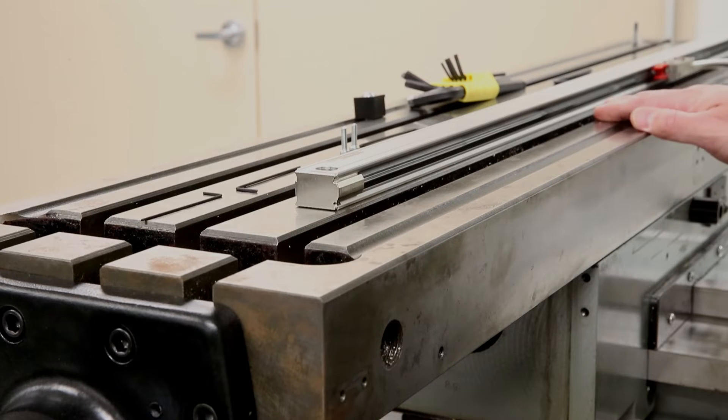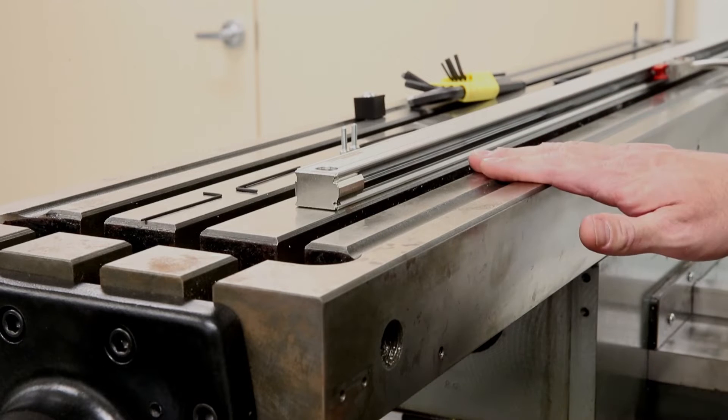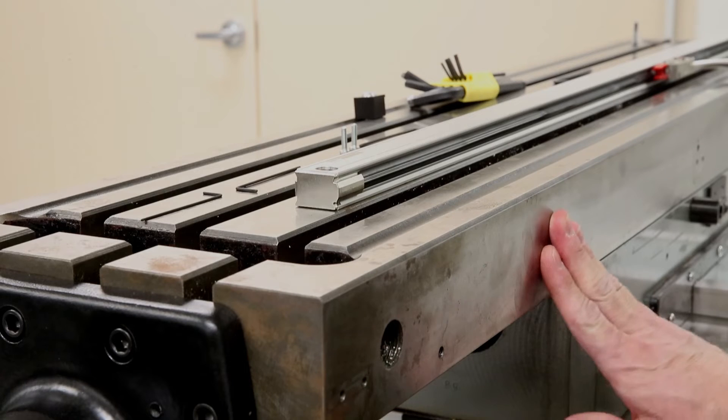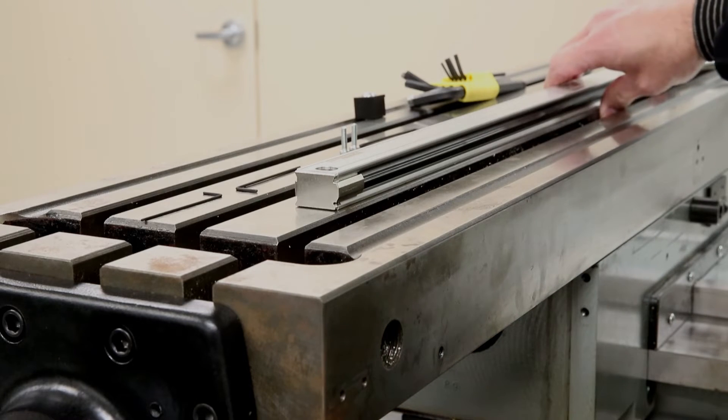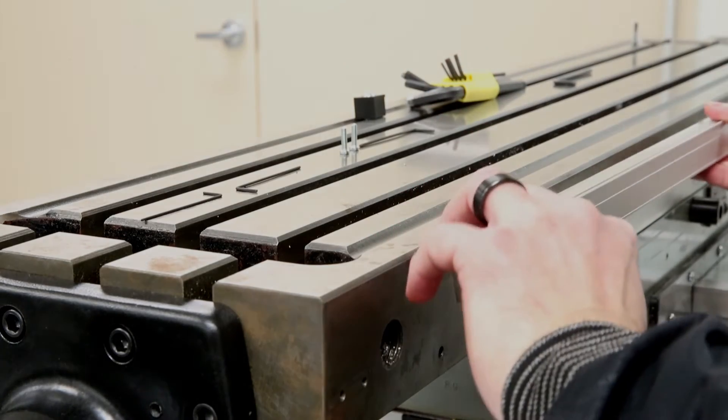Hello, this is how we're going to remount the SCN C150 back to the machine after it has been serviced. Before we took the scale off, we measured with the depth mic from the top of the table to the top of the scale.